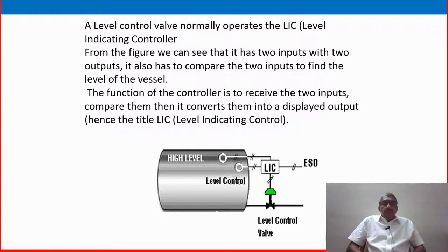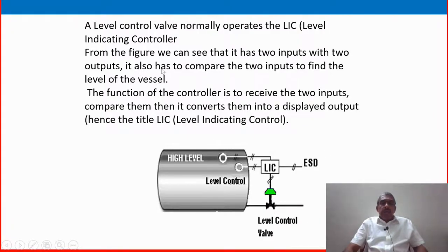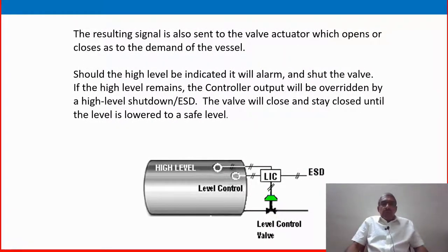Another example is a level control valve that normally operates the LIC — level indicating controller. From the figure, we can see that it has two inputs and two outputs, including an ESD output. It compares two inputs to find the level of the vessel: the normal operating set point level and the high level. The function of the controller is to receive the two inputs, compare them with the set point, and convert them into a displayed output — hence the title LIC, level indicating controller. The resulting signal is also sent to the valve actuator, which opens or closes on demand of the vessel.